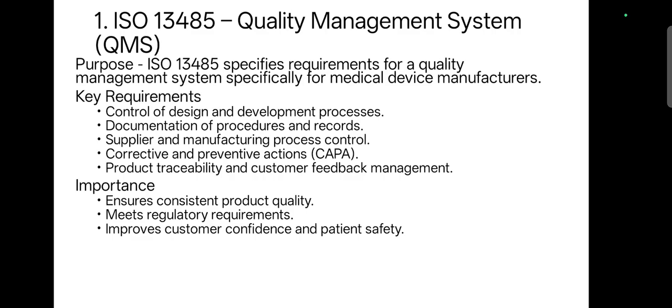Then these are the ISO standards for medical devices. ISO 13485, Quality Management System, QMS, for medical devices. So ISO 13485 is the most important international standard for medical device manufacturers. It specifies the requirements for a quality management system that helps organizations consistently design, develop, manufacture, install and service medical devices that are safe and effective.